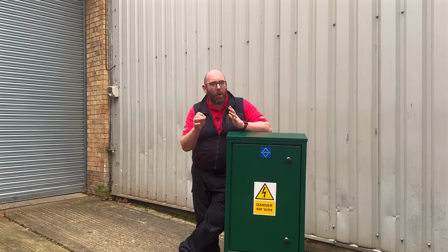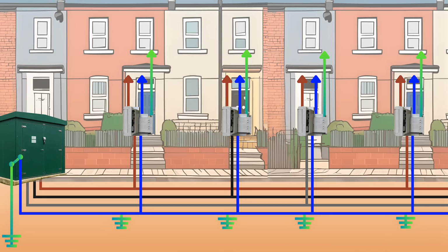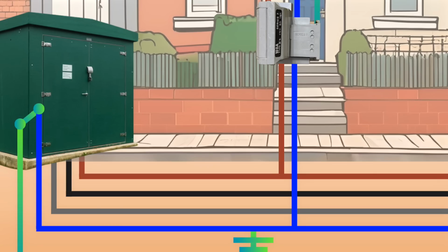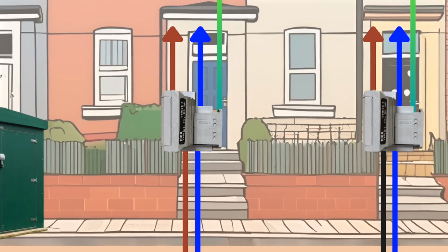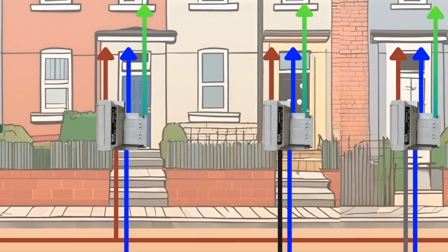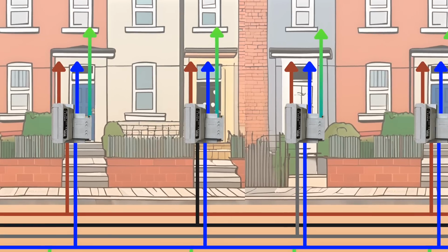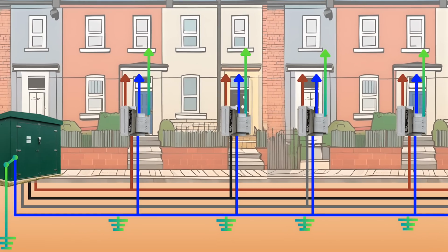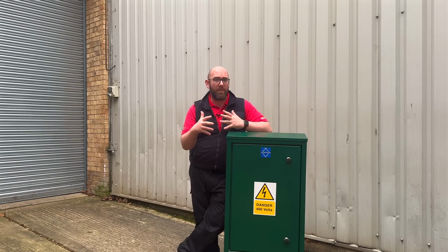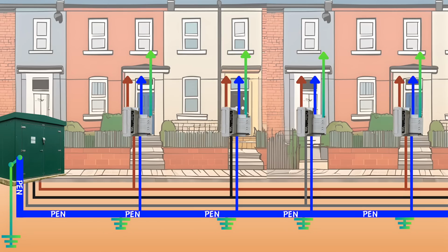But what is a broken PEN? Okay, so let's take this row of houses, all being fed from the substation at the bottom of the street. Each property takes its line and neutral from the supply cable from the road outside. As we can see, the neutral is taken from our star point of the transformer, which is earthed with these rods. This provides the potential difference and makes everything work. This also creates the protective earth and neutral, or PEN, conductor. Right, let's break this PEN and see what happens.